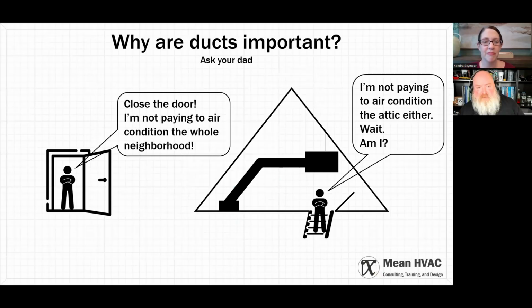Why are the ducts important? From the retrofit perspective, a big factor can be duct leakage. You want a duct system to be well sealed and well insulated, because the same thing your dad yelled at you—we're not paying to condition the whole neighborhood—you're also not paying to condition the attic. If all the connections of the ductwork up in the attic are leaking, that's a problem.